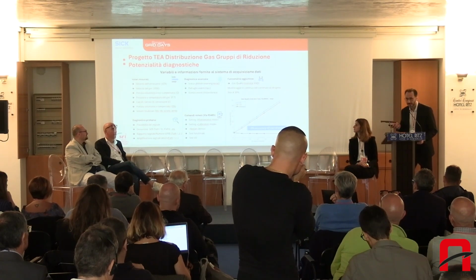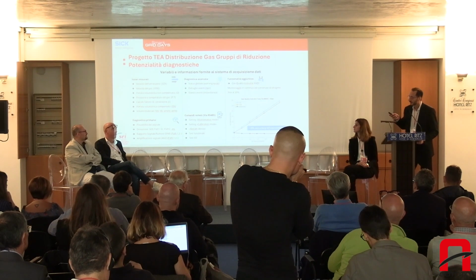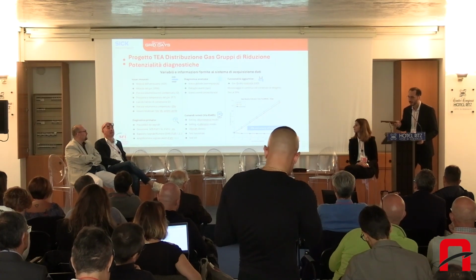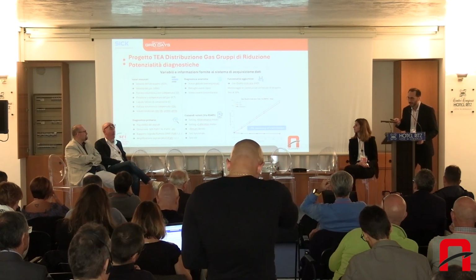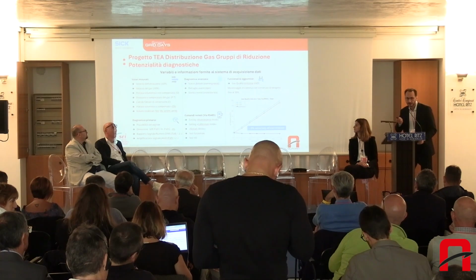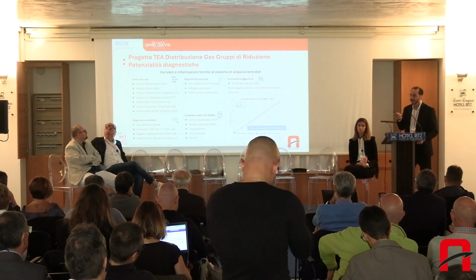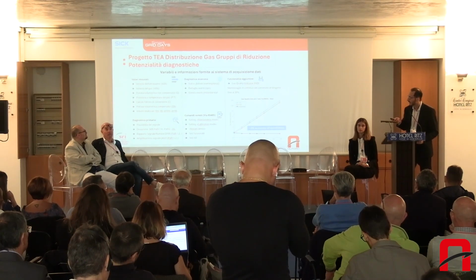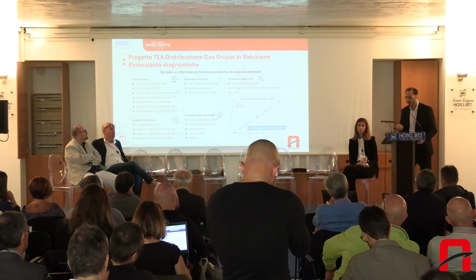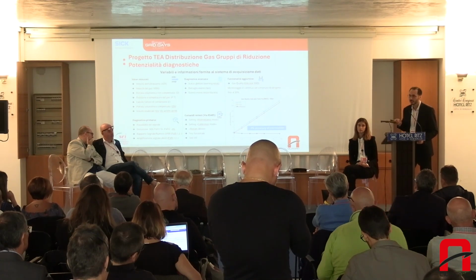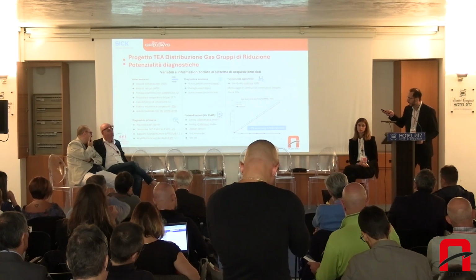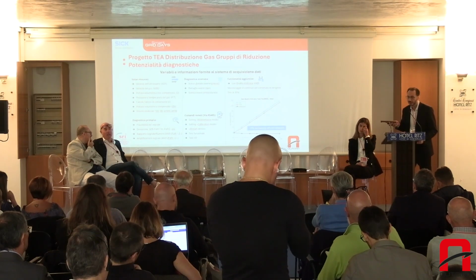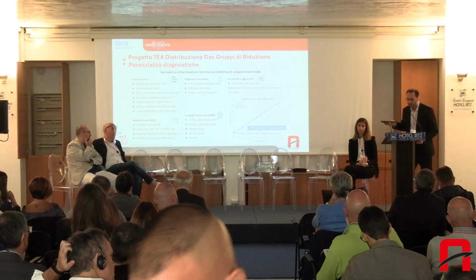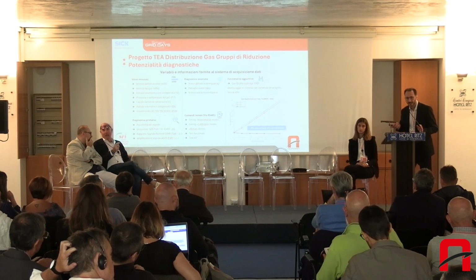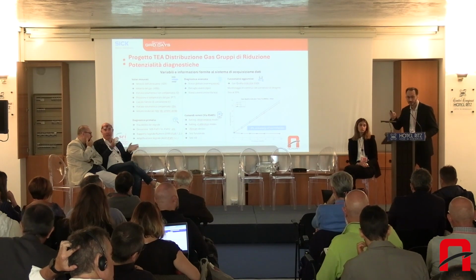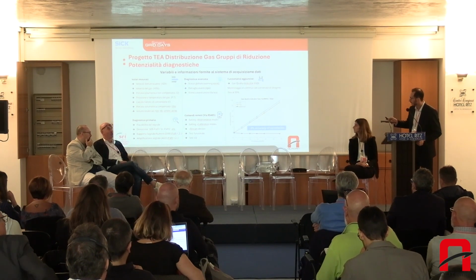We've talked about hydrogen. There are also additional features developed by our group. Through the speed of propagation of the ultrasound, we developed an algorithm that makes it possible to define, for example, in a blend of hydrogen and natural gas, the percentage of hydrogen present in the mixture, with constant monitoring. Also, internationally, a whole series of studies and comparisons were carried out, for example with gas chromatographs, and we've seen that there are very good responses, with an accuracy of 0.1% compared to the readings of gas chromatographs, also carrying out dynamic tests.